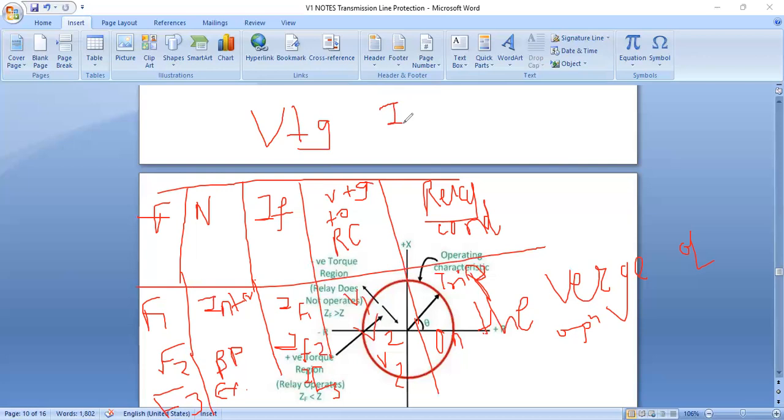That means it is nothing but the IFZ drop. So we can decide the impedance value. You have to search for the product of fault current into Z set, because you have to decide the impedance value so it can be set as the base for the relay operation. If this product exceeds the particular limit, the relay should trip.